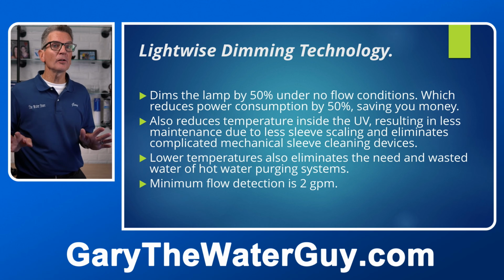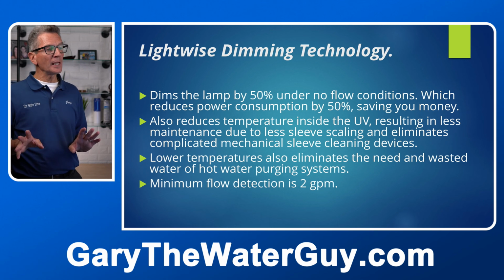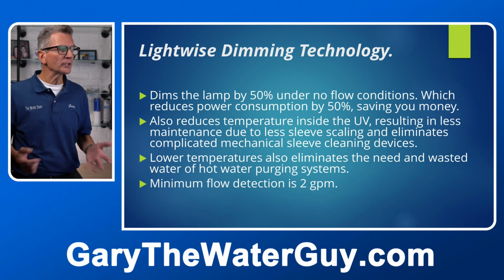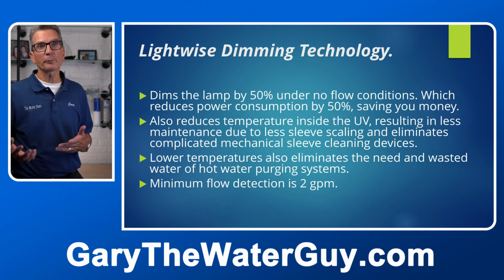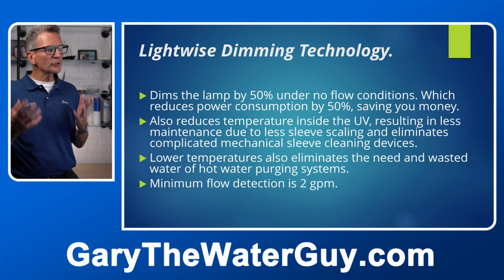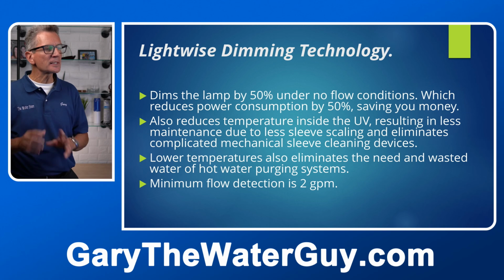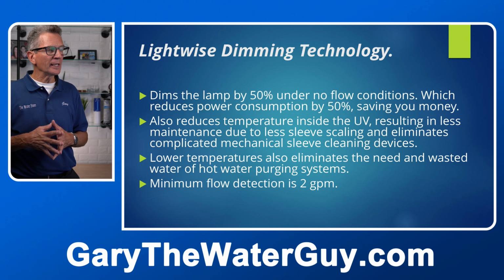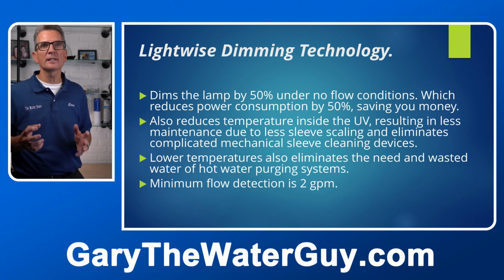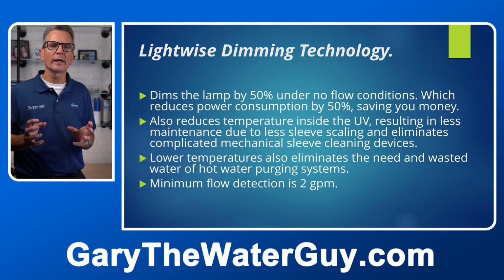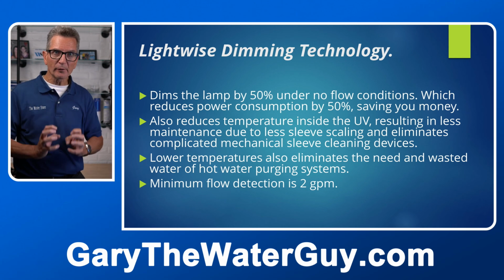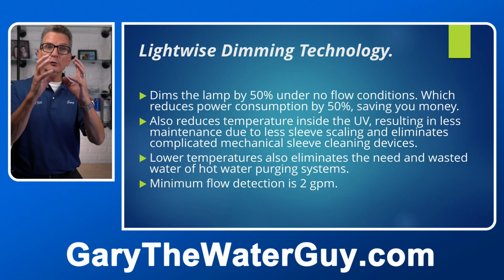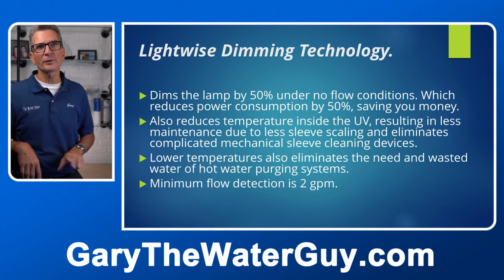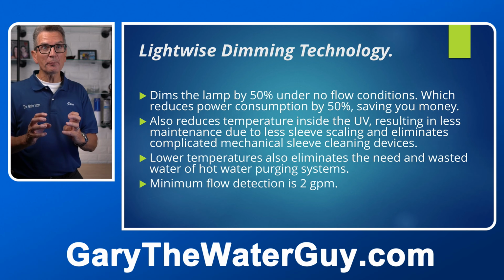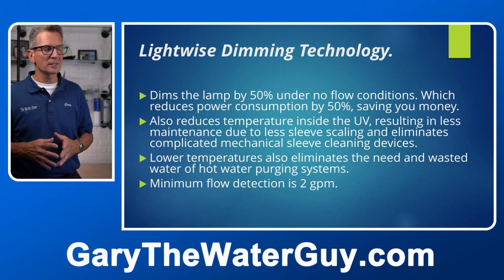This LightWise dimming technology is really special, and here's why. It dims the lamp by 50% under no flow conditions, which reduces power consumption by 50%, obviously saving you money. But it also reduces the temperature inside the UV. And as I say, it results in less maintenance due to less sleeve scaling and eliminates complicated mechanical sleeve cleaning devices. There's some UV systems out there, older ones granted, but there's some out there that actually have scrapers that run up and down the sleeve to remove the scale. Well, because of the lower temperatures, you don't need that. But believe me, those scrapers and the motor that's involved, a lot of maintenance to those systems.